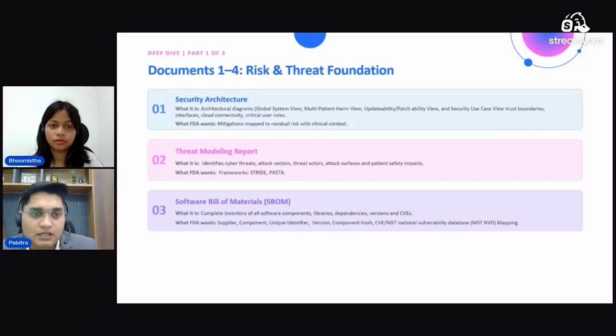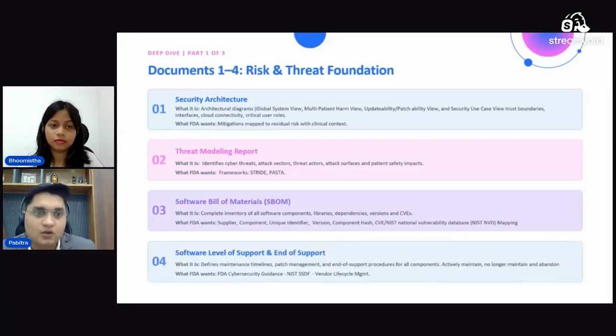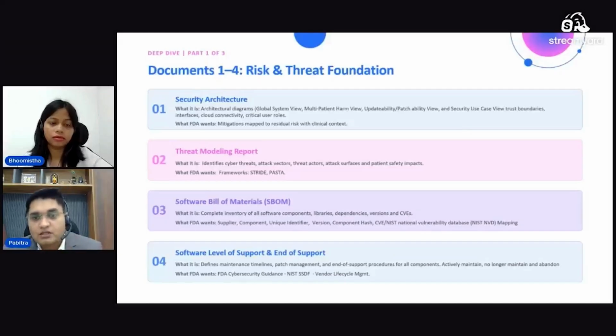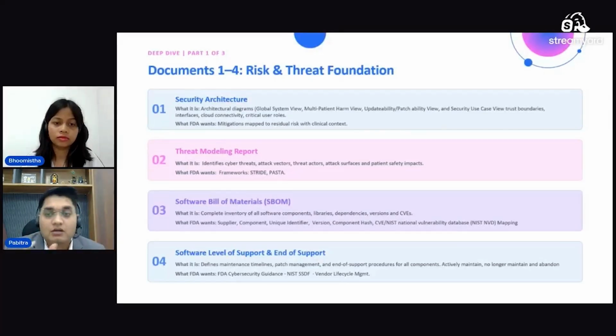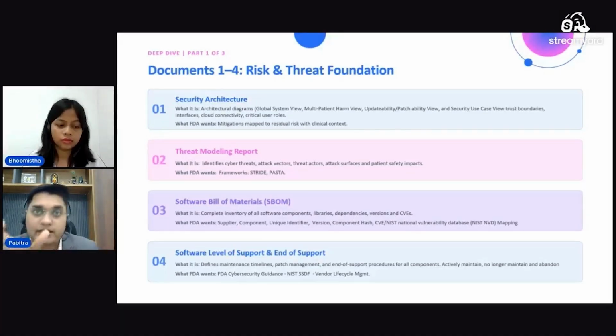And recently a new report has been required by the FDA, which is software level of support and end of support. What is this? If you are using, let's say, a component or a library, you need to state whether that manufacturer is actively supporting and maintaining it, or no longer maintaining it, or has abandoned it. You have to clearly mention it, and if it is abandoned or no longer maintained, you have to write properly how you handle the security. So this is the first stage, during the design and development stage, where these elements and documents can be created.